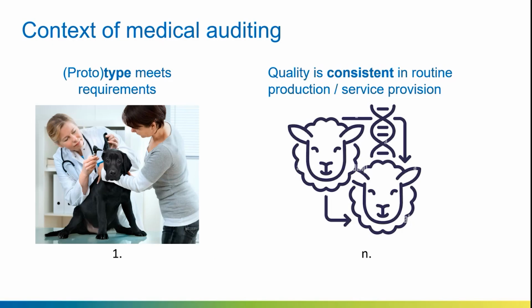But of course, we cannot examine all of the devices to the same depth. And so for that, the second step is that we need to make sure that the quality is consistent in routine production and service provision. So we don't need to go as deep as type testing during routine operation. In some cases, the test that we do in the type testing is destructive and not reproducible. So for example, if you would do a sterility test, you would need to open up all the blister packages for a whole batch, and then you wouldn't be able to release anything. So for that reason, we have to have some sort of a sampling-based system that ensures consistency in the routine manufactured units.